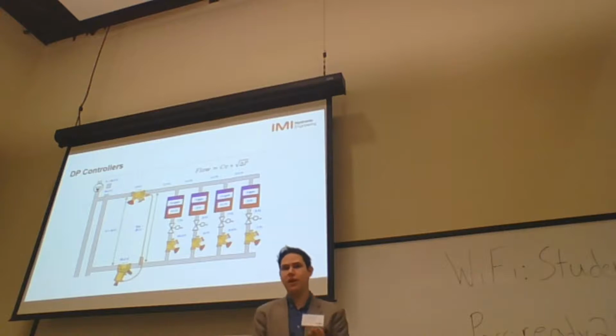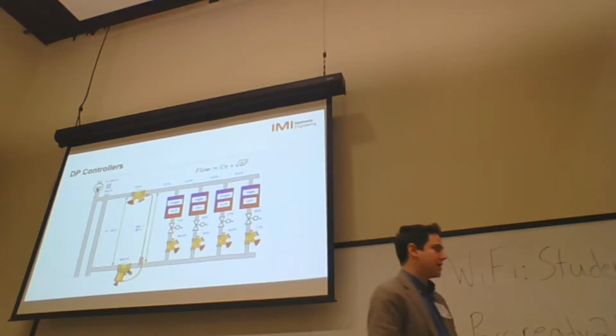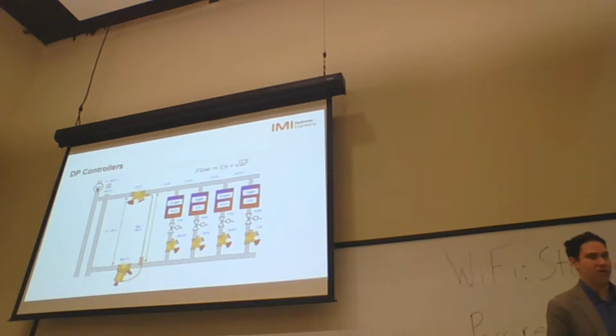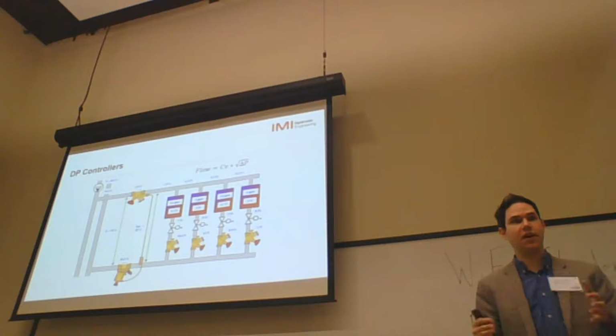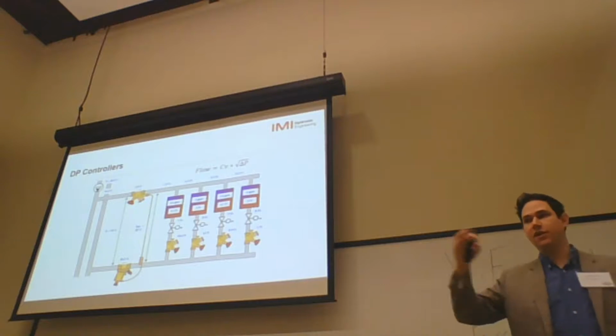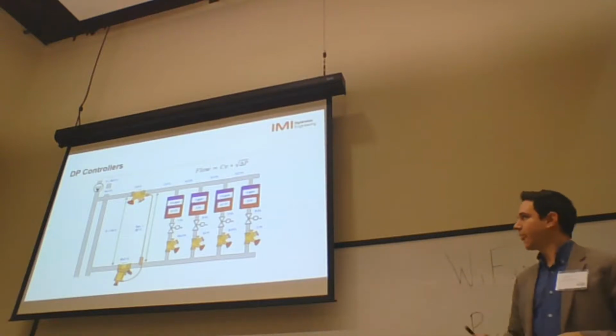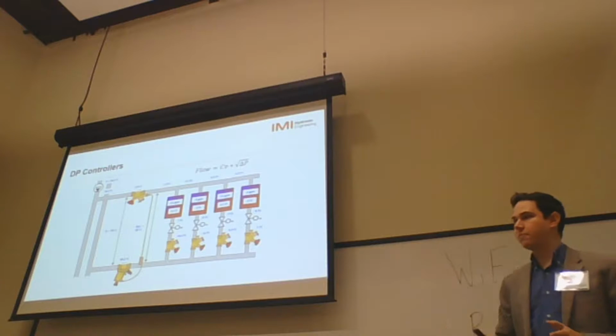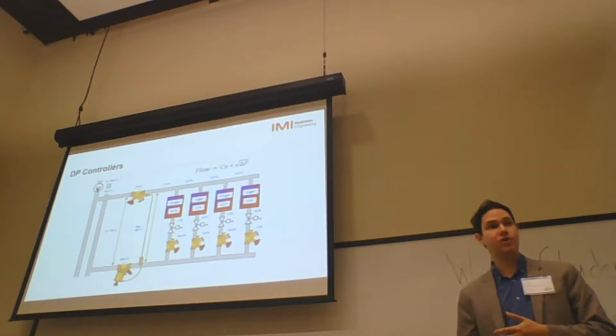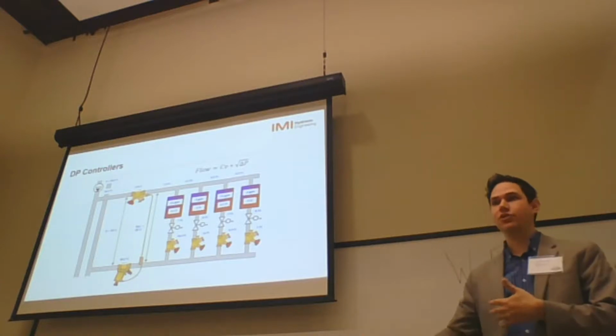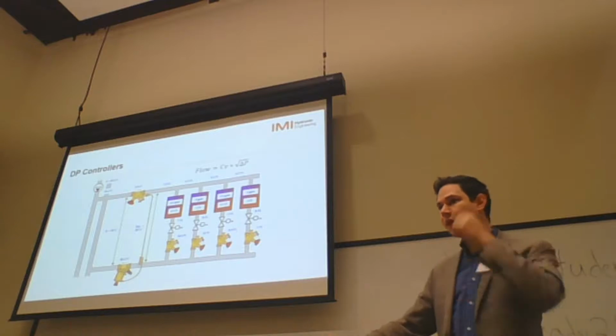As most of you may know, there are a lot of interactions. If I close one balancing valve, it affects all the other parts of the system. If I'm closing another one, it changes all of them again. So there are a lot of interactions between closing one side and increasing the flow on the other side, and the differential pressure controller makes a pressure independent branch and avoids these interactions during the commissioning.